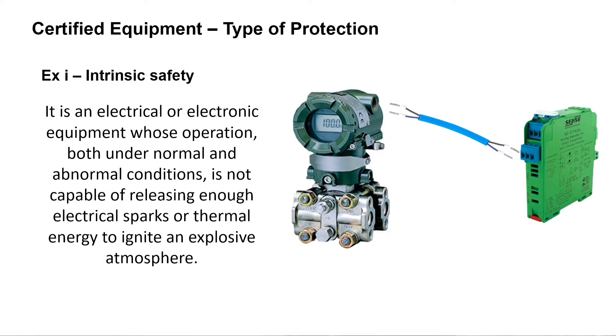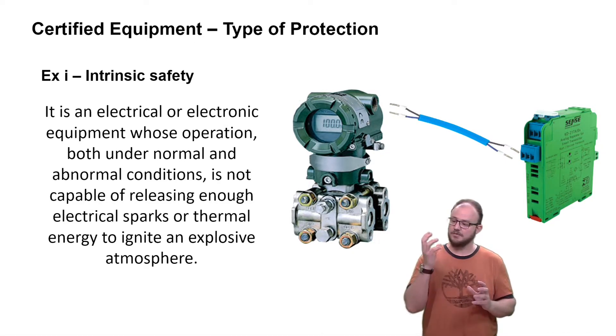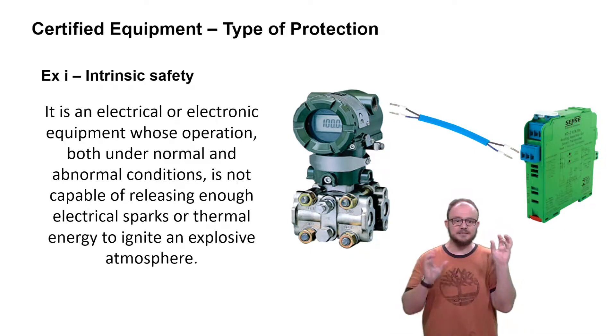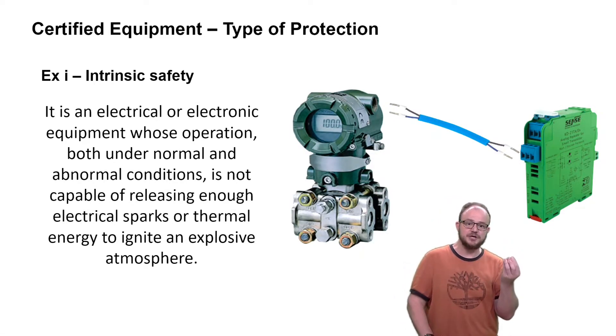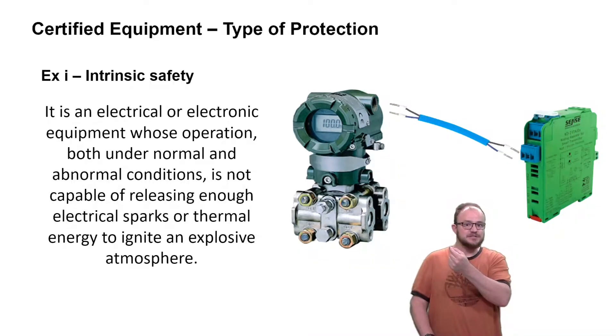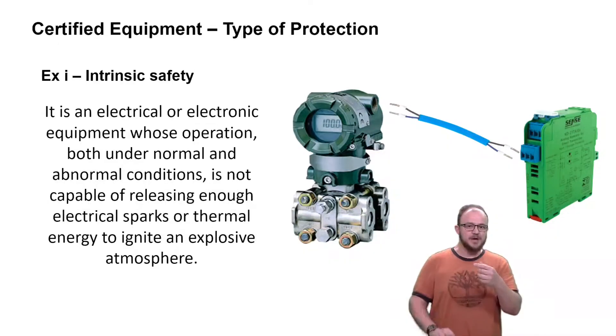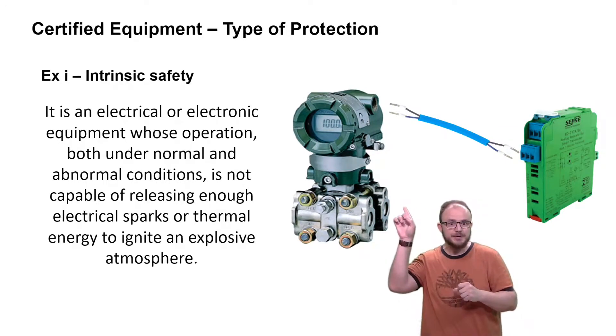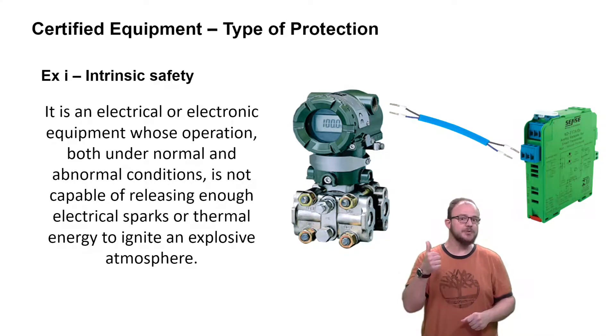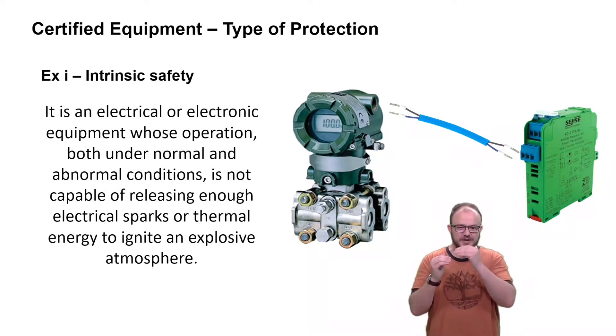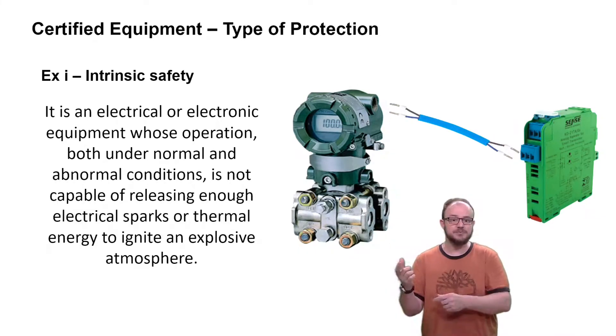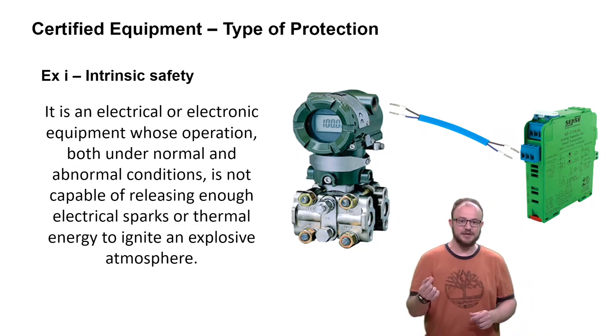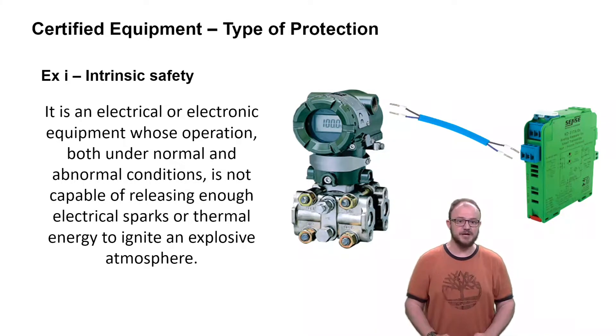We also have intrinsic safety. Intrinsic safe is equipment that works in the field. There is a cable connection and a control source that keeps the ignition source energy as low as possible. This control barrier manages the energy that goes to the equipment, so we will have temperature and sparks, but very low — well below the level needed for ignition. That's why intrinsic safe equipment can be used in Zone 0, because it controls all the energy that goes through that equipment.